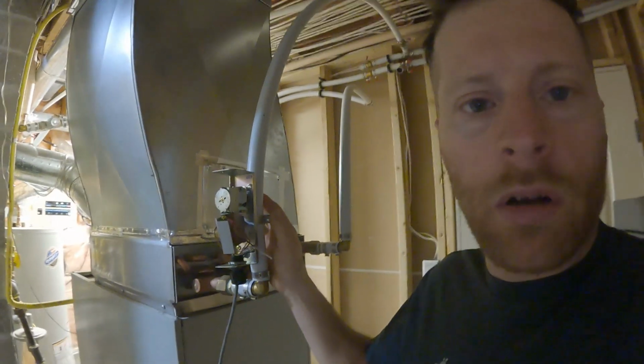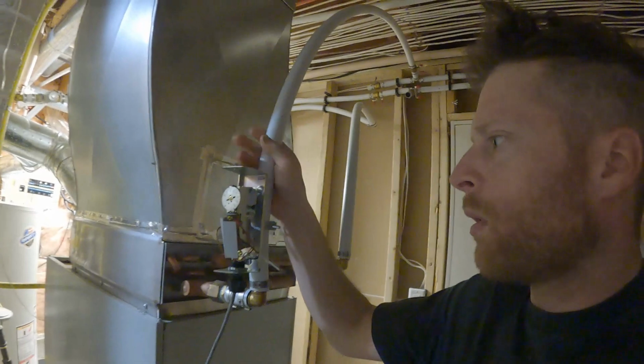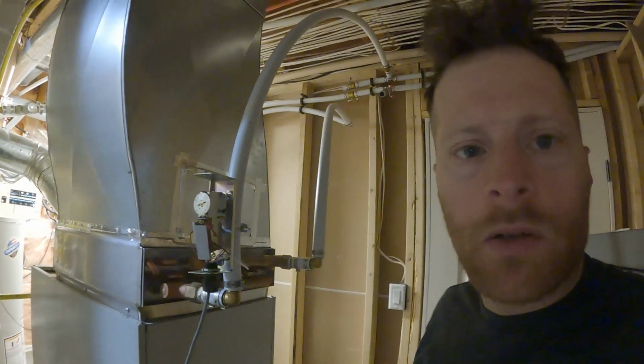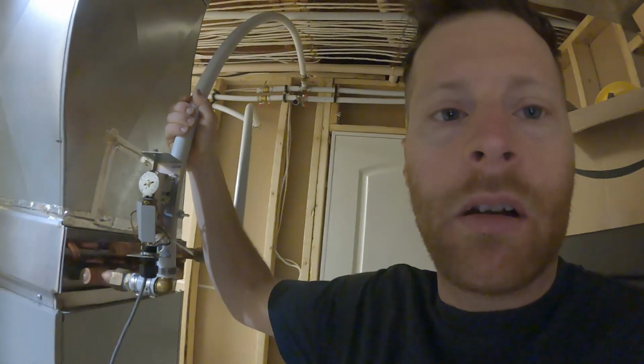Once I had that hooked up, I realized that the Aquastat, which is this guy over here, that we got supplied with the wood boiler, wasn't going to work. It was for a 4-wire thermostat, where our furnace is only a 2-wire. It's quite old. It's from the 70s. So I had to get my buddy Joel out here to take a look at the furnace, and he rewired it, put in a couple relays and contactors, and changed the wiring inside, so that now the way the system works is, if the Aquastat detects that this water here is above 110 degrees, it will fire just the blower on the motor. And if this water temperature drops below that, then it tells the gas valve to kick on, and it'll fire the furnace as if it was running off natural gas.